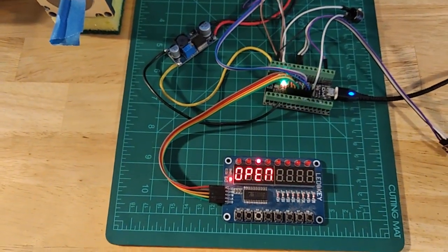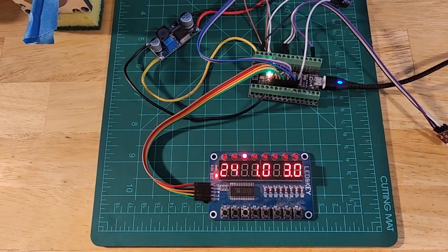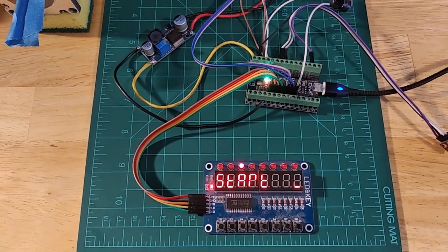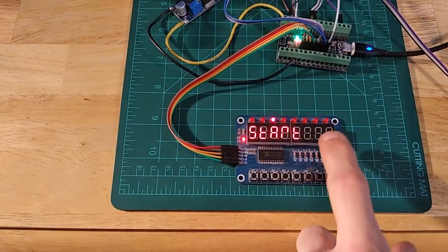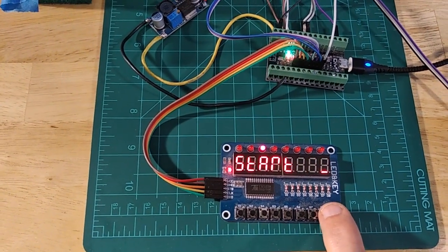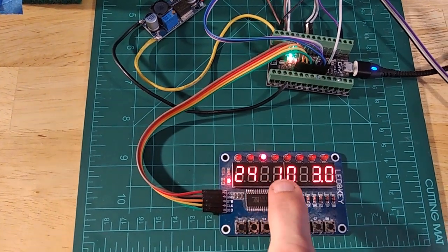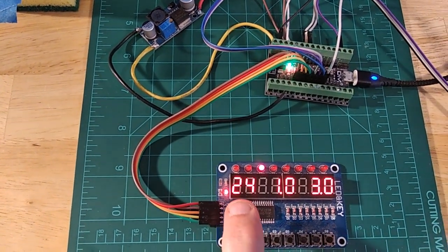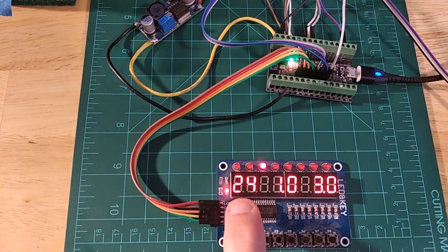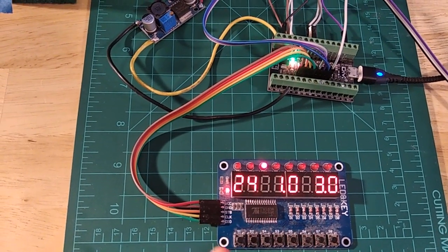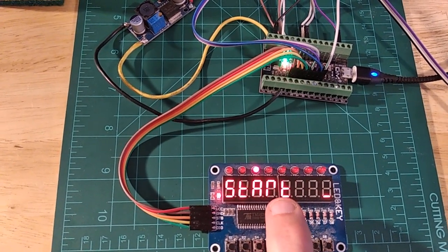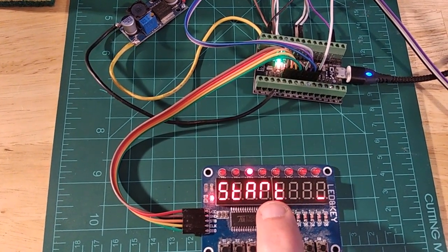So I reset it. So it starts, open source ventilator. And here you have, so it tells you that you can start the machine with this button. It displays 3 data. The first data is the breath rate. So currently it's set at 24 per minute. Then you have the volume, it's in liter. So you have 1 liter.